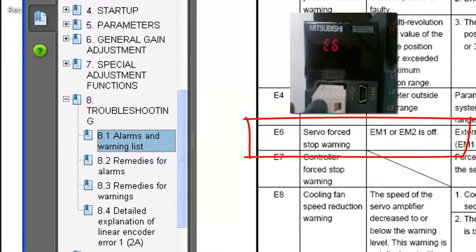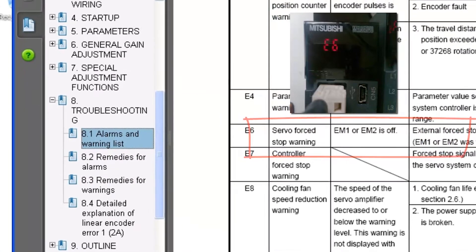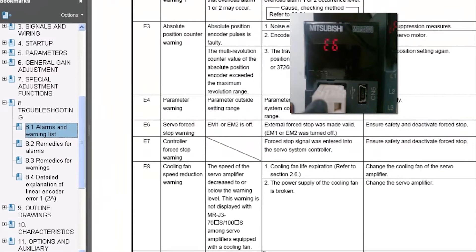According to the MRJ3B safety instruction manual in chapter 8.1, the E6 warning is a servo force stop warning. In order to correct this, you need to ensure safety and then deactivate the force stop.